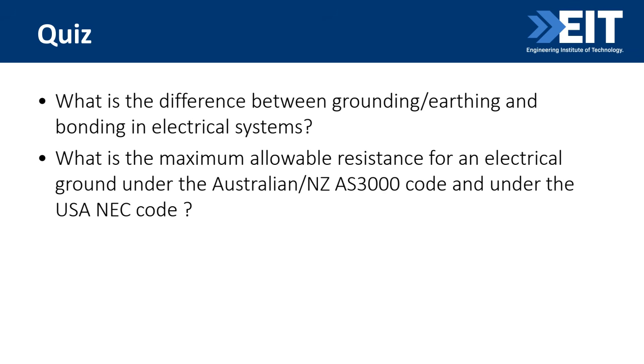How do you measure ground earthing? That's a very good question. There's a whole technique, different techniques to measure the resistance, basically using an ohm meter. But there's a whole approach, because one of the biggest challenges measuring earth resistance, which I can tell you from personal experience, is if you've got any stray electric currents in the area, you could have a problem.